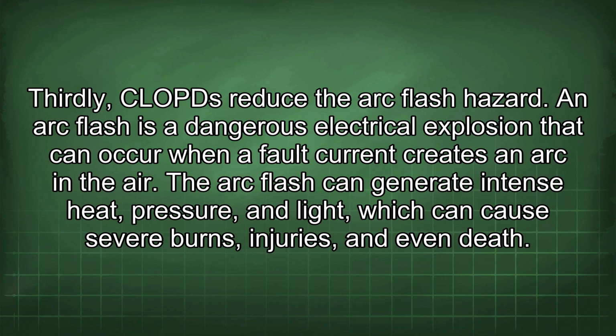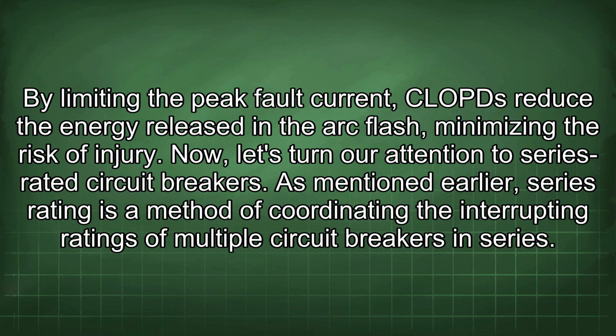An arc flash is a dangerous electrical explosion that can occur when a fault current creates an arc in the air. The arc flash can generate intense heat, pressure, and light, which can cause severe burns, injuries, and even death. By limiting the peak fault current, CLOPDs reduce the energy released in the arc flash, minimizing the risk of injury. Now let's turn our attention to series-rated circuit breakers.